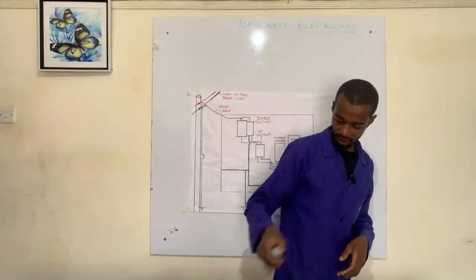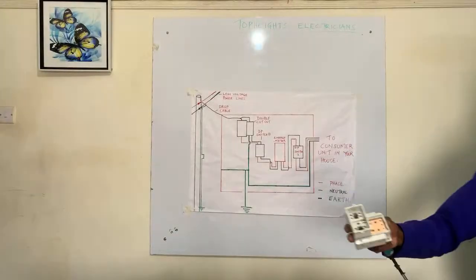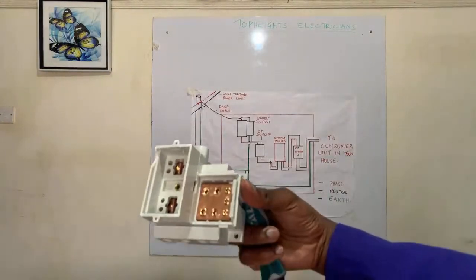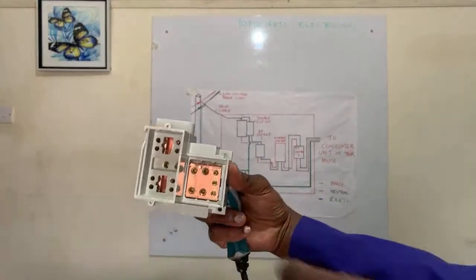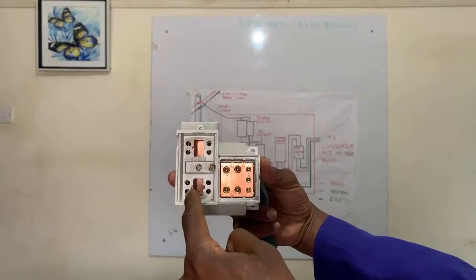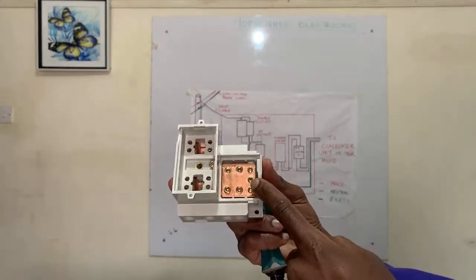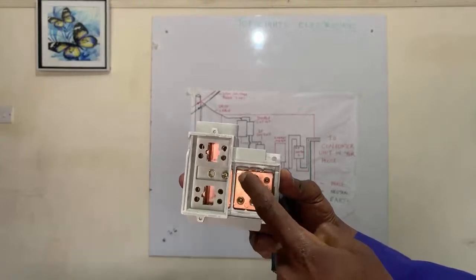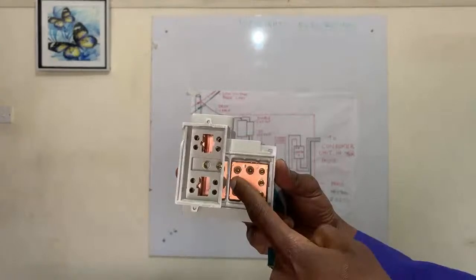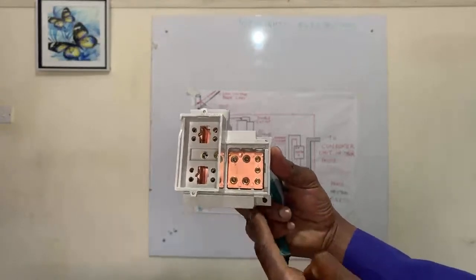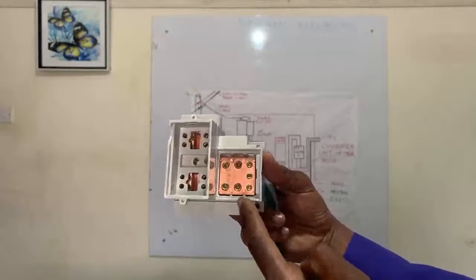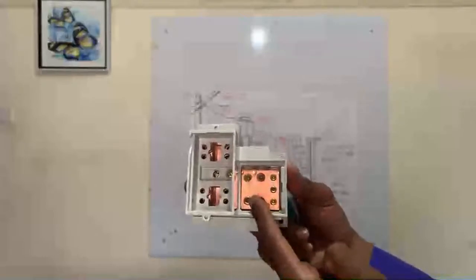And this cutout looks like this. What I have here is a double cutout. So you have the phase here, and then we have this bar. This bar carries the neutral. The neutral will get in here from the supply, and then it will get out here to go to other connections. We also have the earthing connection, also tapped from this line here, so that the earth connection will go to the consumer unit, as well as the one going to the earth rod.